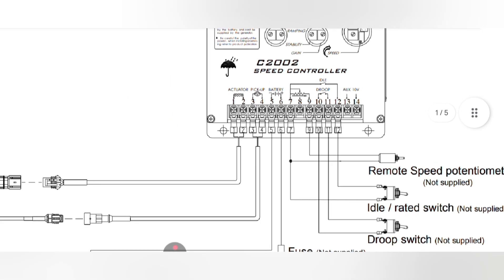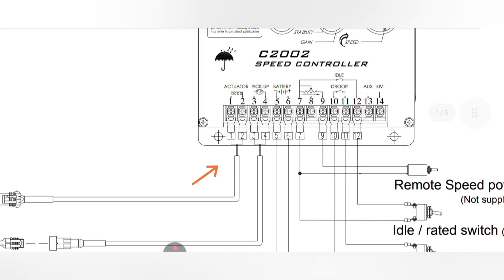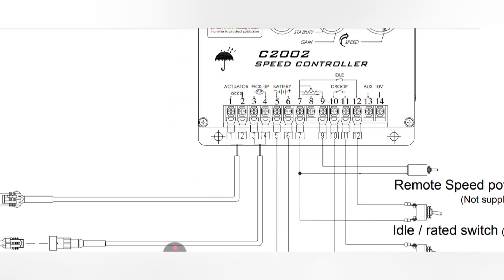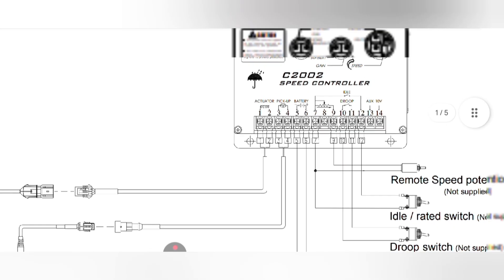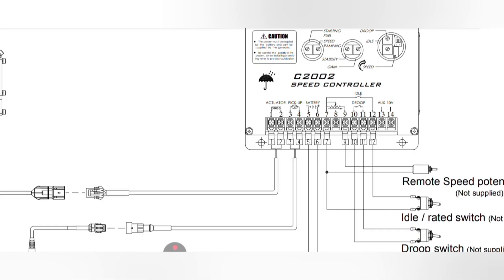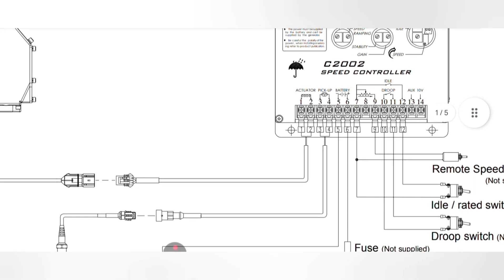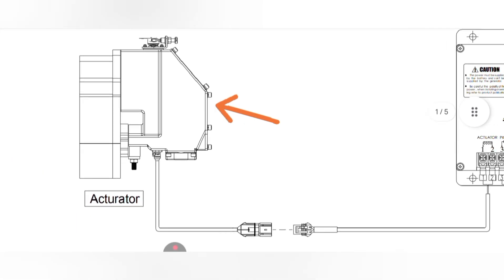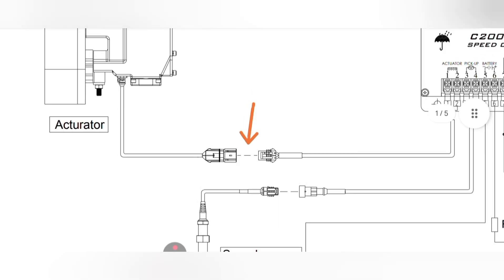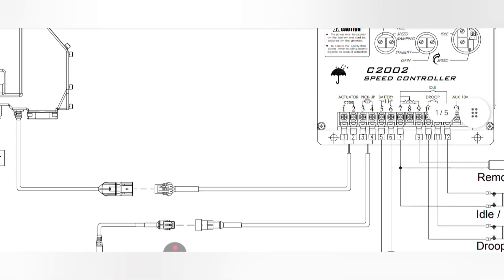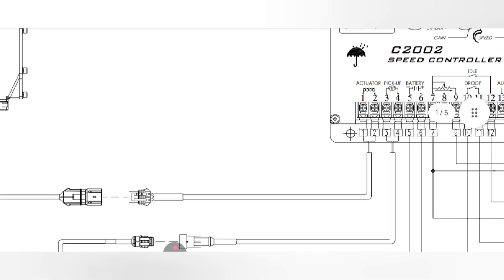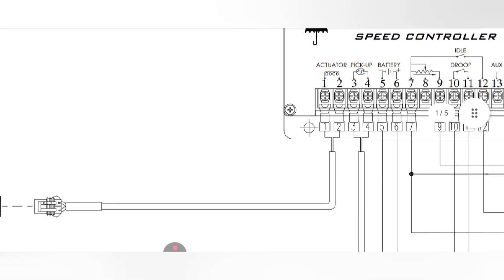Here is the overview of the C2002 speed controller. The terminal block has 14 pins for inputs and outputs. Starting from the left side: pin number one and pin number two are the output to the actuator. These two wires carry AC generating current out to the actuator. As you can see, the actuator connects via a two-wire coupler connector in the middle.